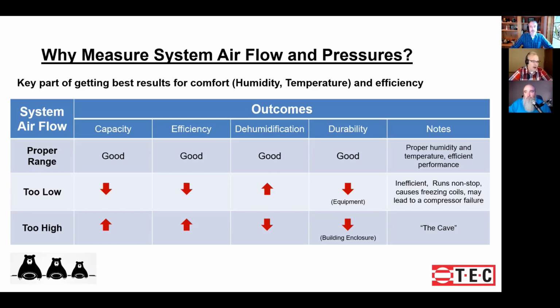So, if it's in the proper range where it should be per the design, then all those things are going to be right in the range they should be. But if it's too low, your capacity goes down. Not only that, but your efficiency gets worse if the airflow is too low. Dehumidification goes up, and now that can be a good thing, and you need to understand if you need to design for that. But if airflow is too low, then actually dehumidification starts to go back down, and the durability of the equipment can be at risk. You can start to have problems like coils freezing up and liquid going back to the compressor if the airflow is very low. Right.